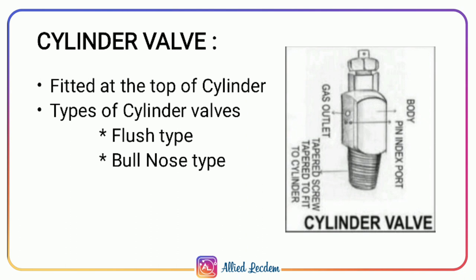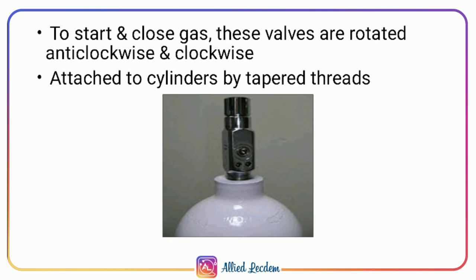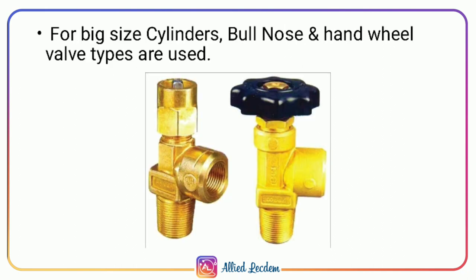The cylinder valve is the most important component of gas cylinders — it is the port through which gases are released, fitted on top of the cylinders. Types of cylinder valves are flush type and bull nose type. To open the cylinder, the valves are rotated in an anti-clockwise direction; to close, they are rotated clockwise. They are attached to cylinders by tapered threads. For big size cylinders, bull nose and hand wheel valve types are used.